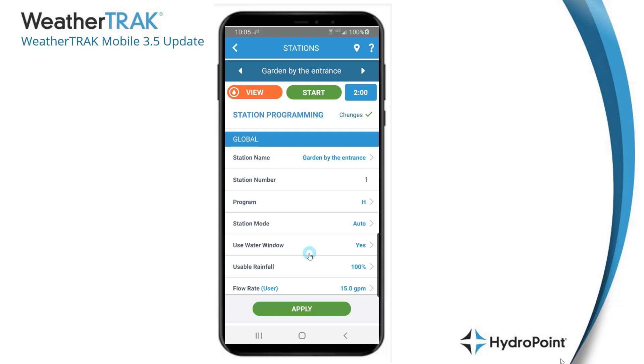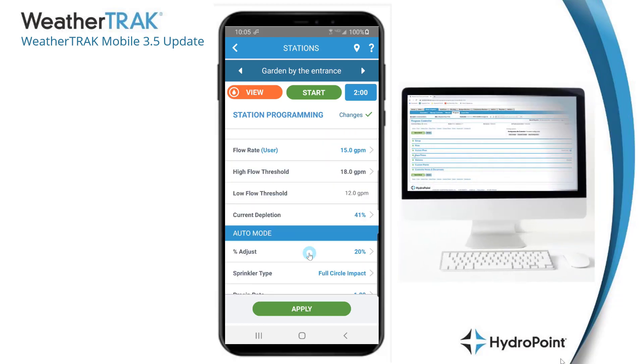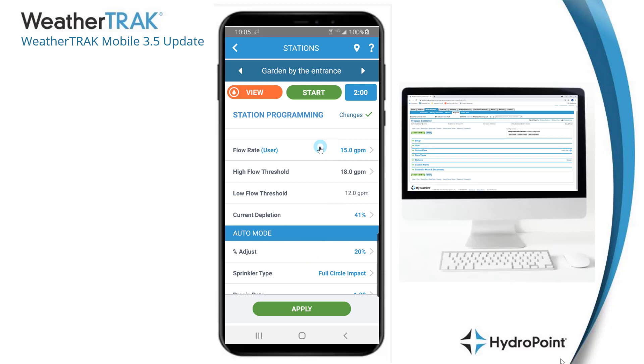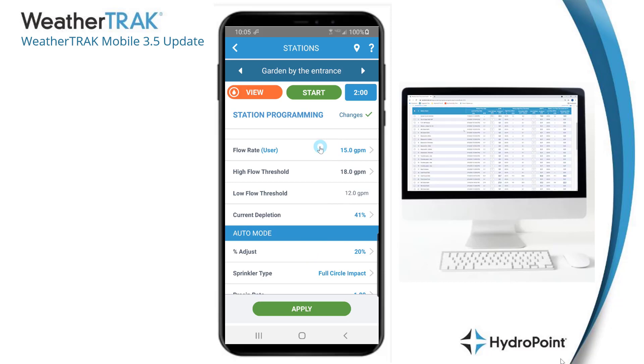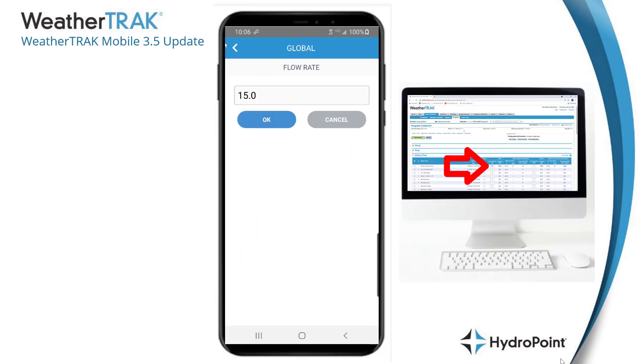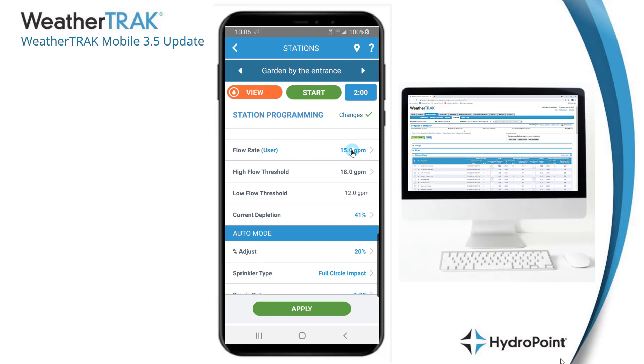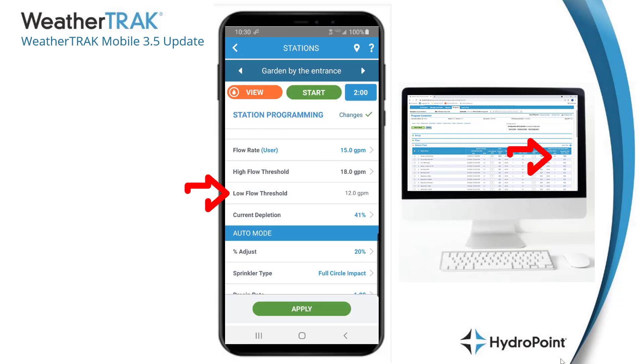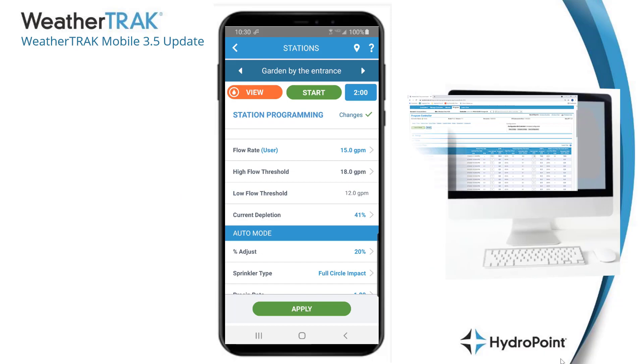As we scroll down, we start to see things that are new and different with WeatherTrack Mobile 3.5. Specifically, we have the ability to not only view but manage station flow settings. If you're out in the field troubleshooting a flow issue and want to put in a user-defined flow rate or assigned station flow value, you can change that from the app. You can also change the station high flow threshold, and you can see — but not edit — the station low flow threshold.